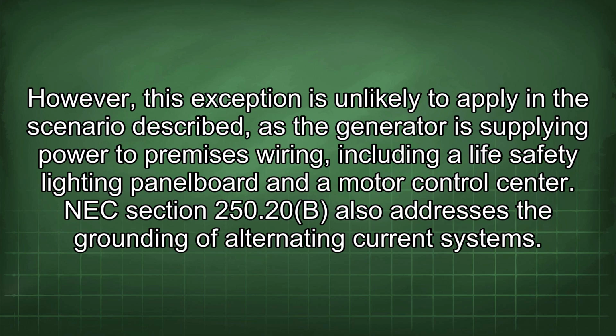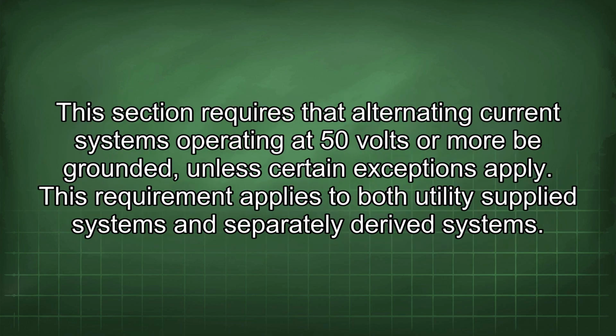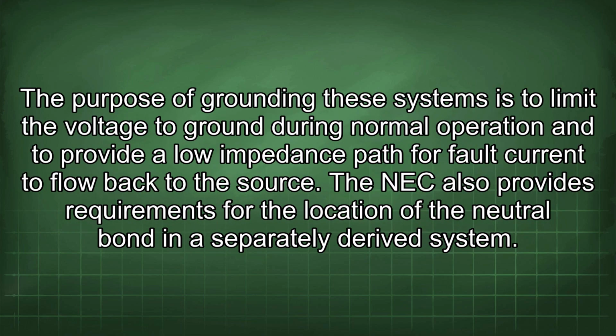NEC Section 250.20(B) also addresses the grounding of alternating current systems. This section requires that alternating current systems operating at 50 volts or more be grounded, unless certain exceptions apply. This requirement applies to both utility-supplied systems and separately derived systems. The purpose of grounding these systems is to limit the voltage to ground during normal operation and to provide a low impedance path for fault current to flow back to the source.